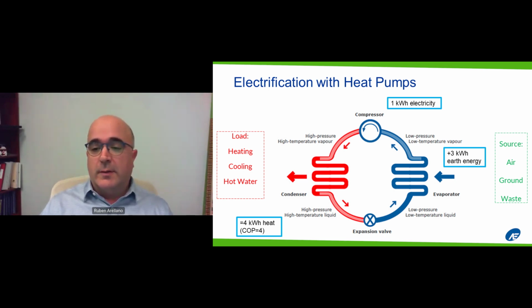With some basic elemental examples: we might take 3 kilowatt hours of Earth energy, say, from the ground. The heat pump will use 1 kilowatt hour of electricity to operate, but it moves that 3 kilowatt hours to a building space, so as a result we have 4 kilowatt hours of heat in the building space. That essentially is what we'd call a COP of 4, or a coefficient of performance of 4.